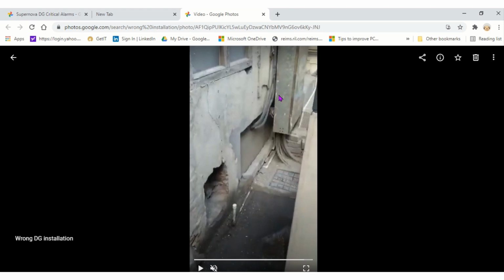So anyway, on the suction side there is hot air. Further, this hot air will become even hotter through the radiator, and again it is moving around the DG sets. So this area is a completely hot circuit of air, and this DG will never get cooling properly on either side, and because of that this DG cannot even run on its standard load condition. Even with very minimum load, the DG will give a high temperature alarm and tripping. So it's not a healthy environment for the DG to run, because a wrong kind of installation has been done.